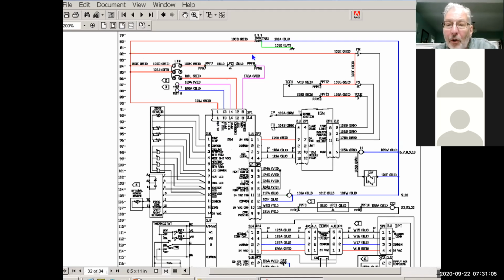But remember now, this power also feeds other things. It goes through the pressure switches and some of the safeties. It also feeds this low voltage terminal board, and it also feeds the number 12 pin here, which is our emergency stop. So we could drop this emergency stop out, drop power to this board. Nothing's going to run, but as you can see here, the light's still going to come on the main board. So just because the light is on doesn't mean the phase monitor is not the problem. This emergency stop might be open. Check these different places for voltages. So if you have voltage here, and you have voltage here, lights on the board, and it's not running, it could be again emergency stop, could be phase monitor, could be almost anything.